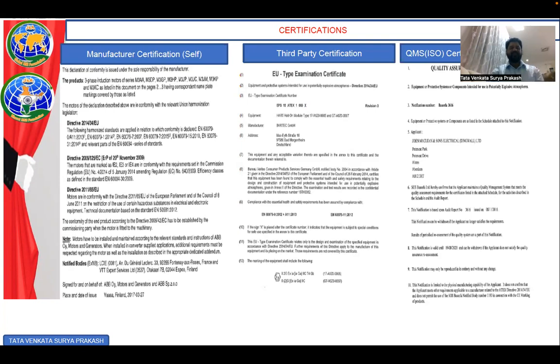So periodical inspections are very important. Predictive and preventive maintenance practices as per ATEX requirements need to be conducted on each vessel, conducted by an approved inspector. For example, API vessels should have an API certified vessel inspector conduct the inspection, and there is certain criteria to follow - 100% thickness needs to be tested, pressure testing has to be done again, etc. These guidelines should not be skipped, because in the end, the effective functioning of a vessel or system deals with the life of people working in the vicinity of the zone.